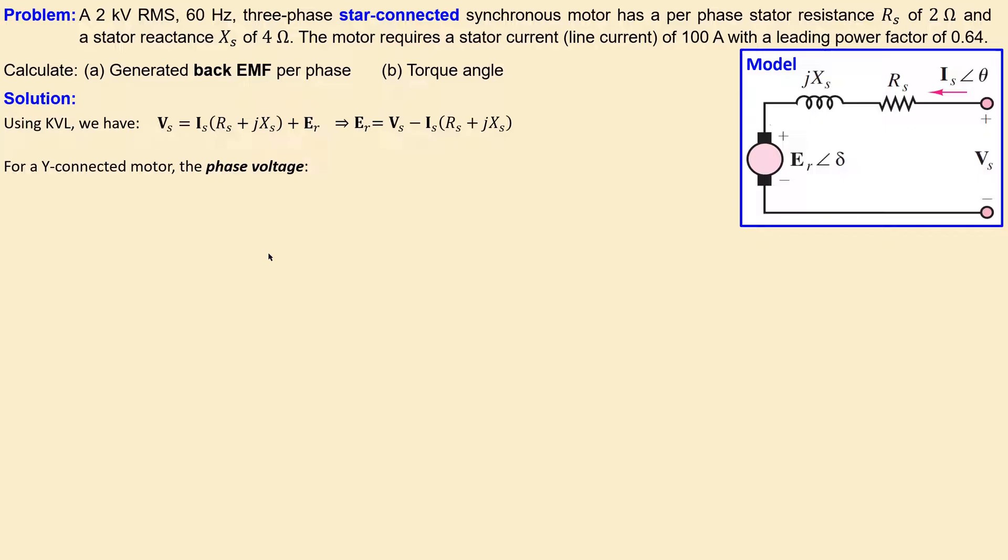For a Y-connected motor, the phase voltage Vs is the line voltage over square root of 3. We have 2000 volts RMS, so this will be 2000 over square root of 3, which equals 1155 volts RMS.